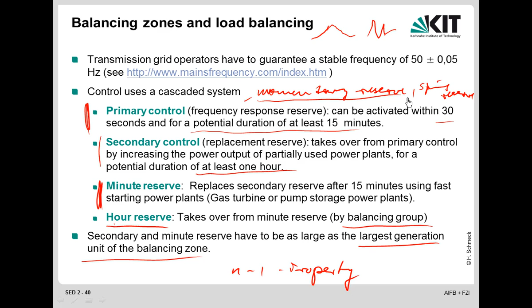And now all those spinning turbines are being reduced in numbers. And so this Trägheit of the system is reduced. That means that if before you had changes in frequency like that, it will be more like this in the future. Much faster, more dynamic changes in frequency, because you will have less of that momentary reserve. And then you need more momentary reserve at other places where you never thought of as being able to provide momentary reserve. And in one of our projects in grid control, we are working exactly on that, to provide momentary reserve from power storage, like from supercaps, because they can step in immediately if there is a loss of energy, and then can step in for a short moment, and then other devices can take over. Okay, so this is the momentary reserve that is also there.